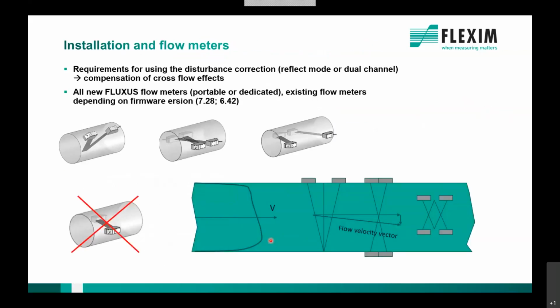So what is the installation requirement? We have to install it in reflect mode when having a single channel meter, or if you have a dual channel meter, you can use one of those installations as an X mode, that's what we call it, or a displaced X mode installation. Some people call it a V mode, both mean the same. Why do we have to use it that way?